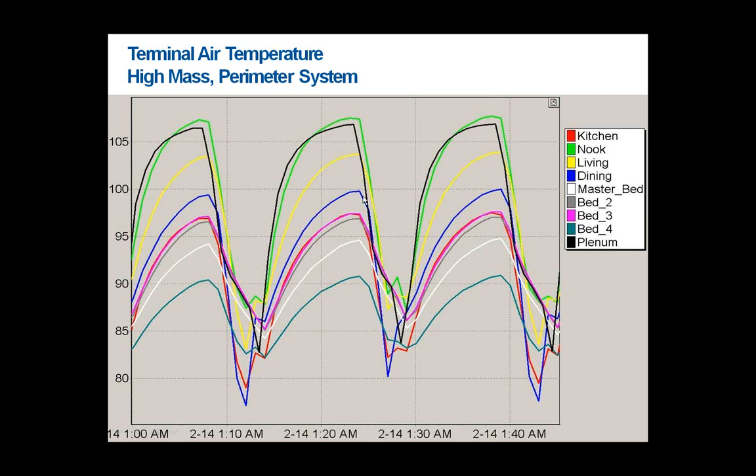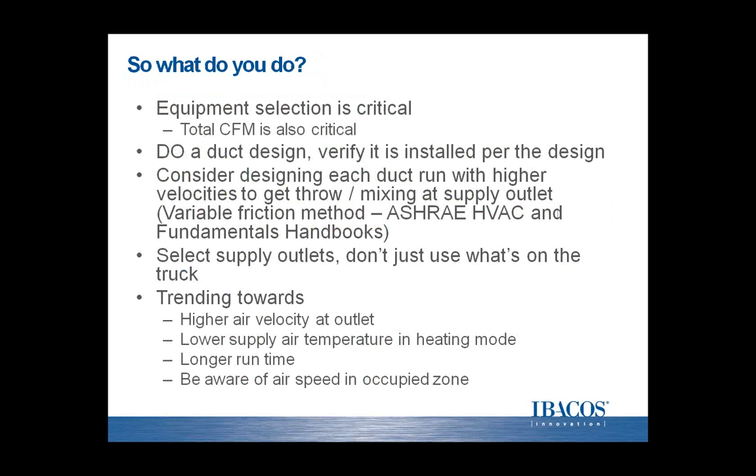This is where air balancing perhaps can be problematic, that if you're simply balancing on an absolute uniform temperature of air coming out of there, you may be providing more air to the spaces that need it less, and starving air from other rooms that could be using it more, not because the air flow itself is wrong, but the temperature of the air varies as you get the length of runs in these systems. So doing more compact systems, using materials that have a lower mass for heating up or cooling down can be beneficial in the designs of the system.